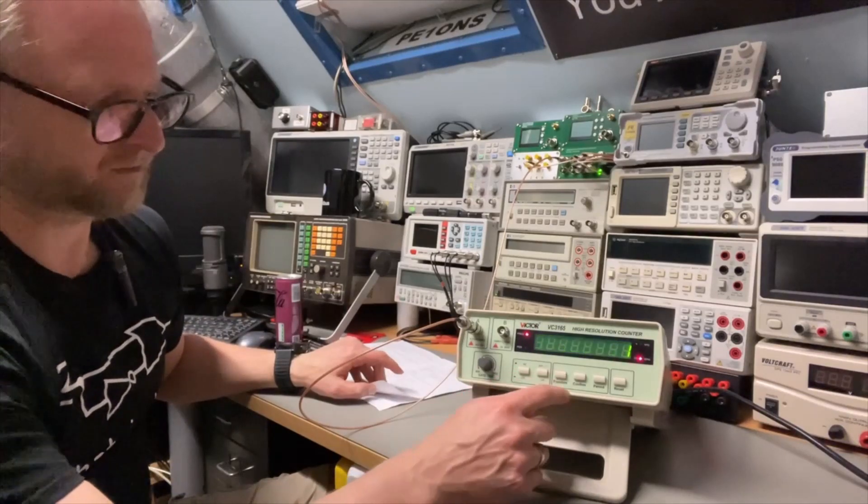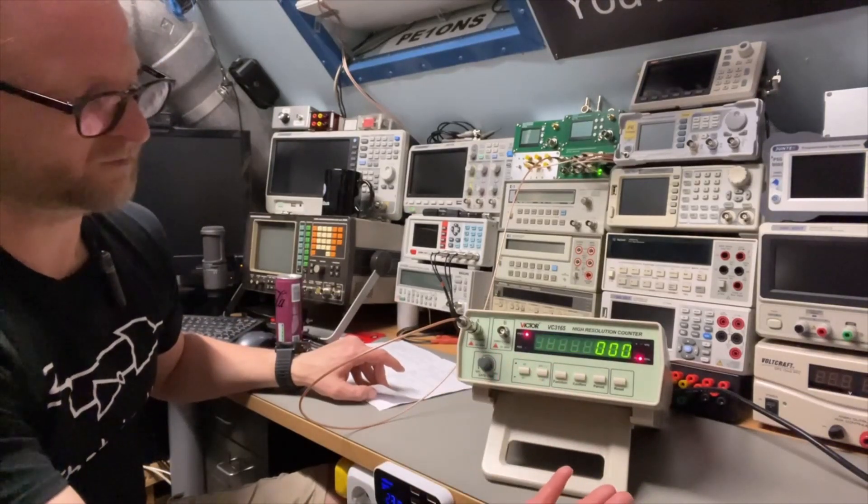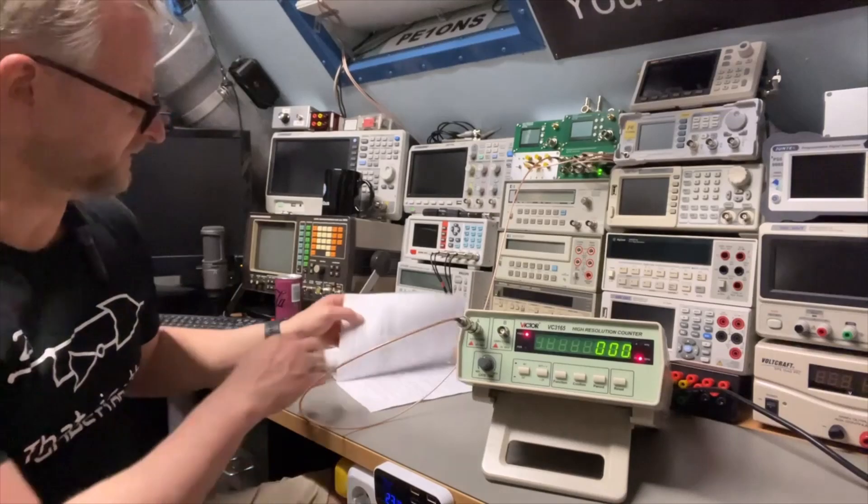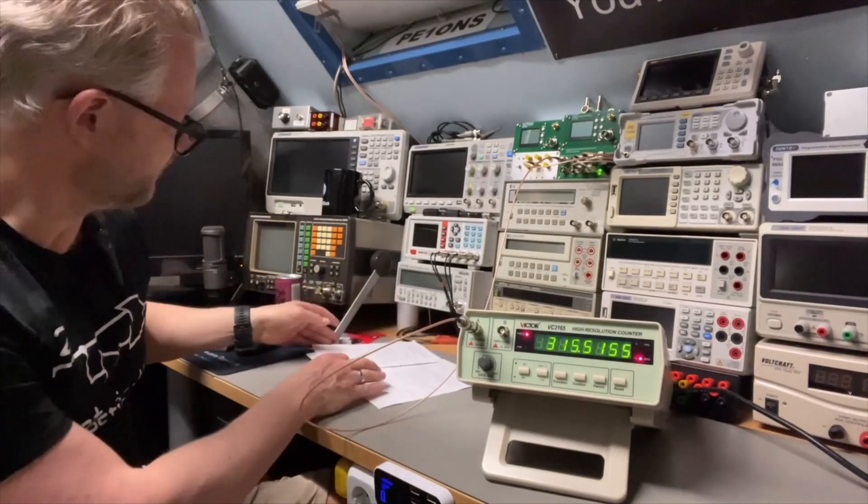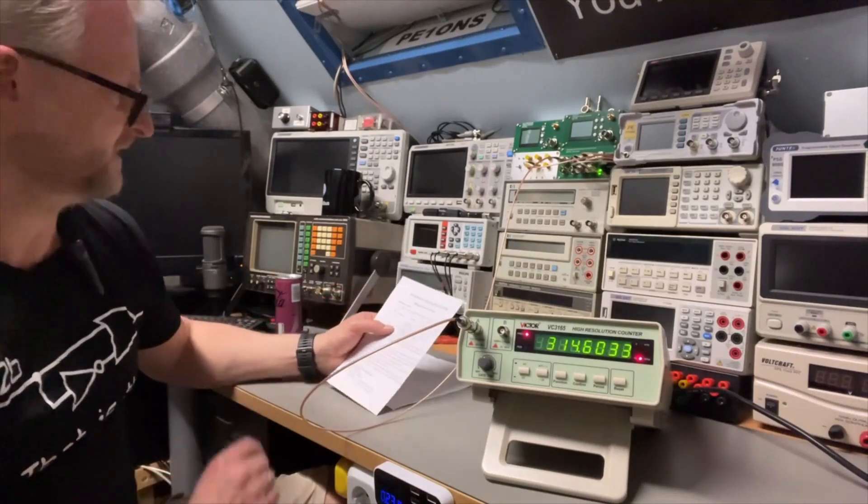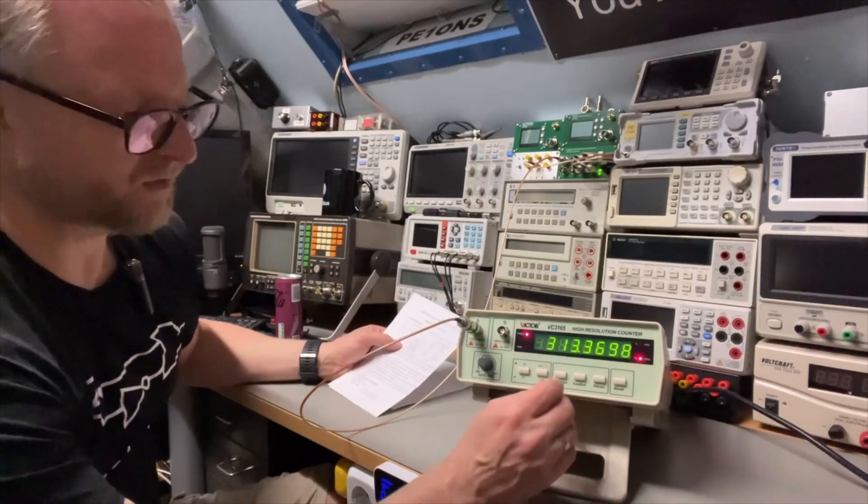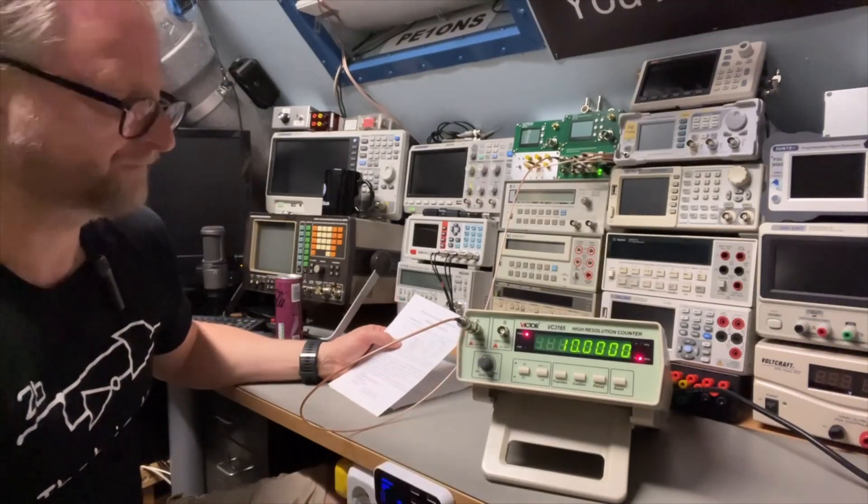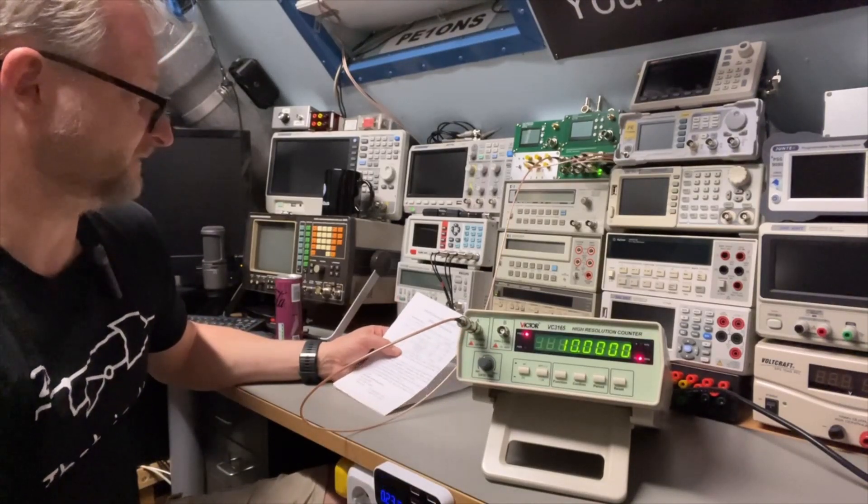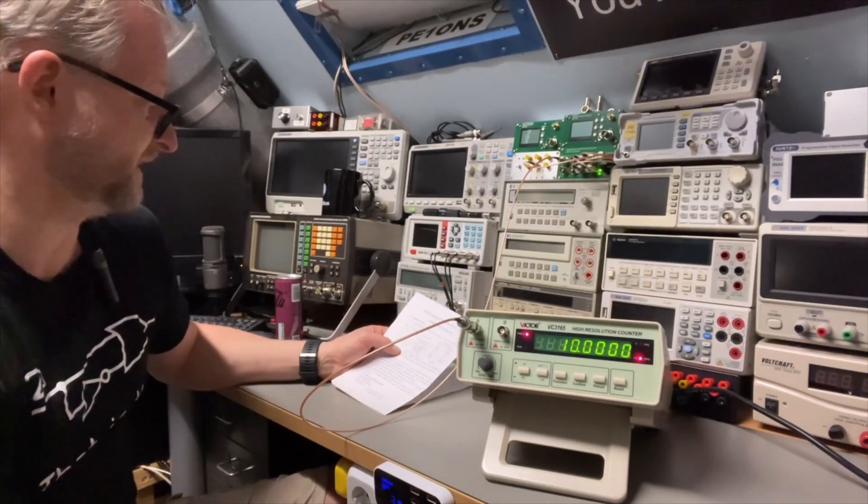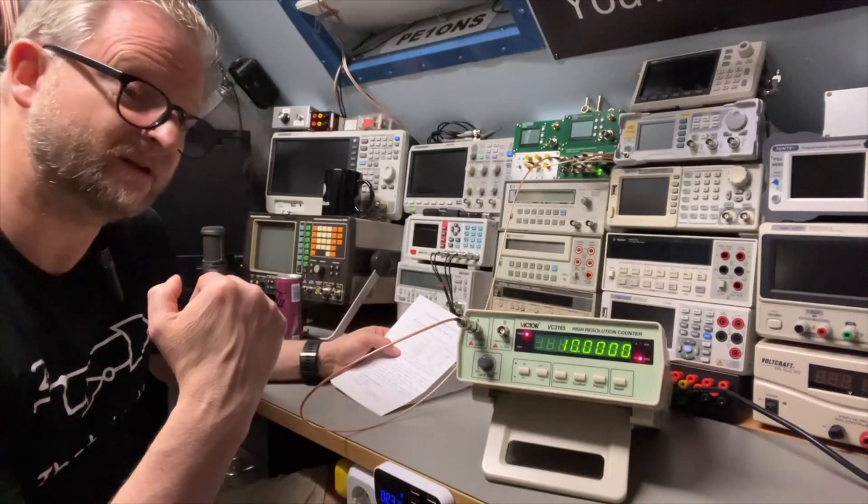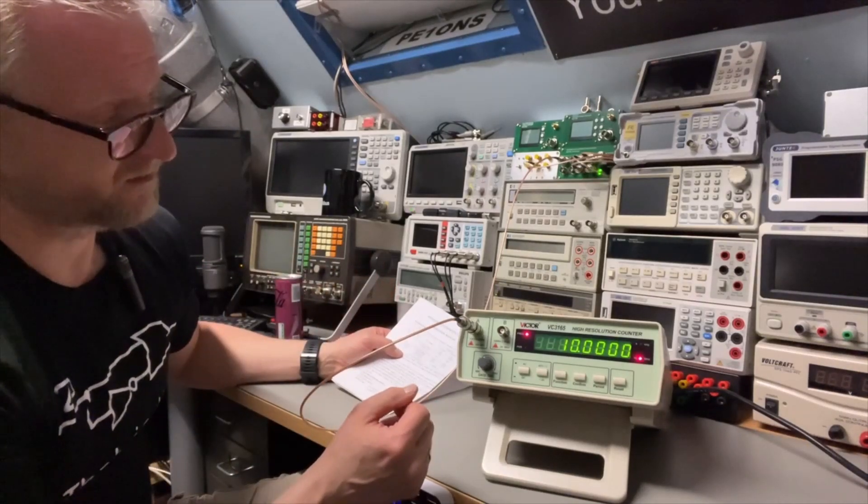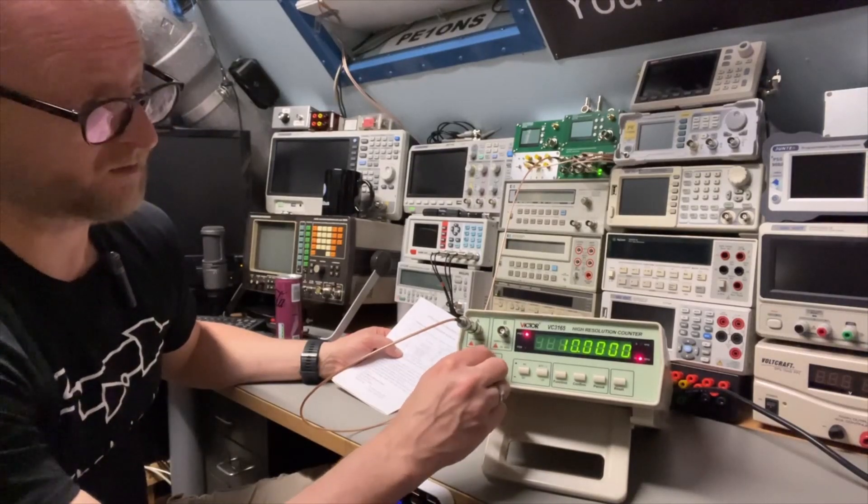So how do we get this A port working? I decided to do this with functions. Function one is the default for the high frequency port B. Then there is also a function two and function two works on the A port. There is also a function three and function three does the same but then they have a low pass filter and the higher frequencies are cut off above two megahertz.